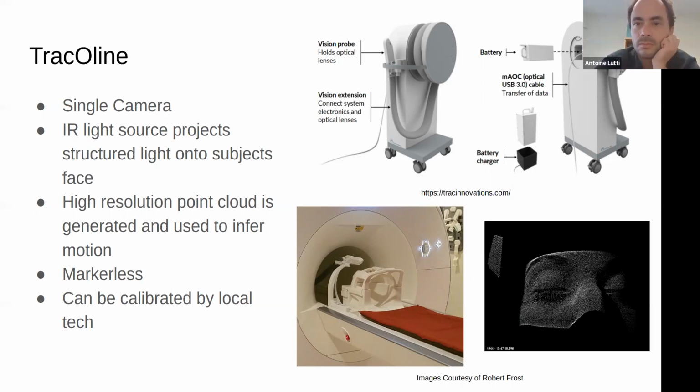That will extend the duration of your scan, but for patients with a lot of motion, it's probably worth it, right? Like if you're doing a 6-minute structural, you can dial in 12 minutes worth of reacquisition time, right? So in theory, you could get every TR twice if the motion was that bad, and that is probably better than getting two 6-minute structurals that both might be motion damaged.